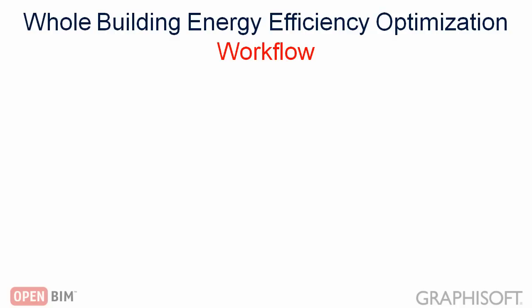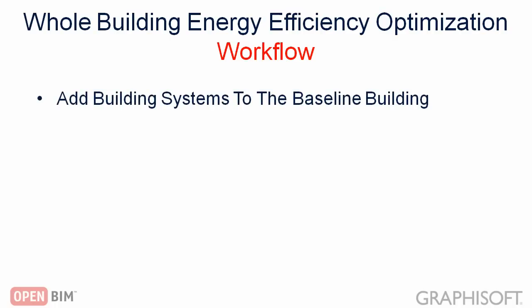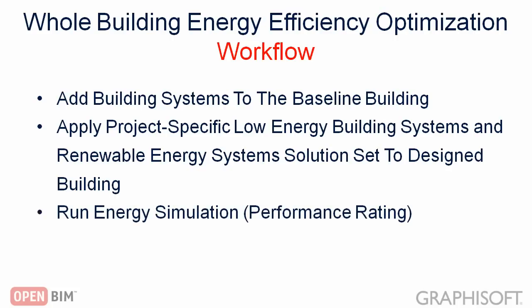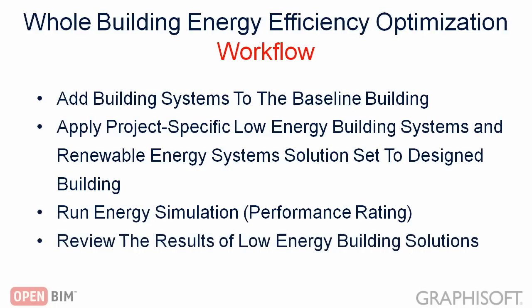Let's review and summarize the whole building energy efficiency optimization workflow. Start by adding building systems to the baseline design and saving the energy model in baseline building reference file format. Size the designed building systems based on the results of the previously executed energy demand calculation. Use Sensitivity Analysis to determine the project-specific low energy building system and renewable energy system solution sets, then apply them to the proposed building's energy model. Assign the baseline building reference file to the designed building's energy model before executing the hourly dynamic energy simulation in performance rating mode. Review and document the designed building's energy performance rating results.